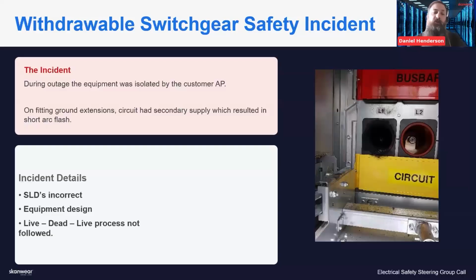Which is probably the most important - that live dead live process wasn't followed. Even if they'd been shown it and fully believed everything was correct, they should have done their live dead live check before inserting any tool into that orifice. The guy's been very lucky in this incident, but it shouldn't have happened if they'd followed the process.